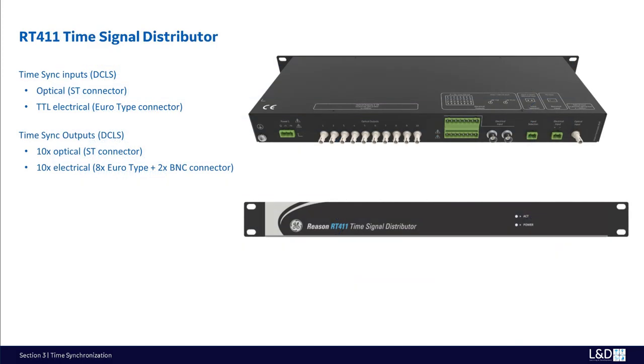The Reason RT411 time signal distributor is a cost-effective way to synchronize multiple devices in the substation. It works as a time signal transceiver providing up to 20 time outputs from a single input, such that the expense of installing multiple GPS antennas in the substation is avoided.